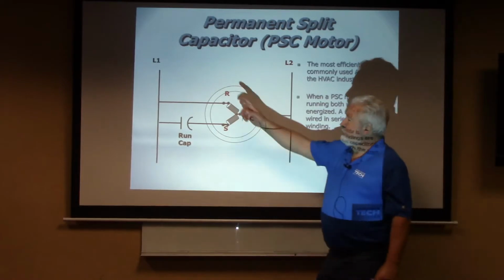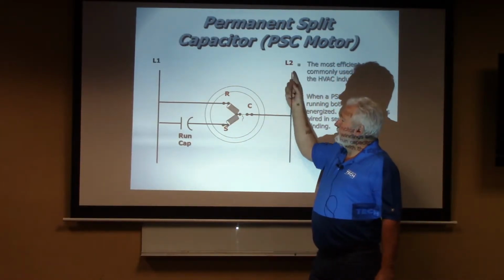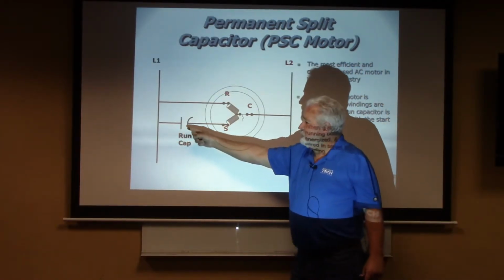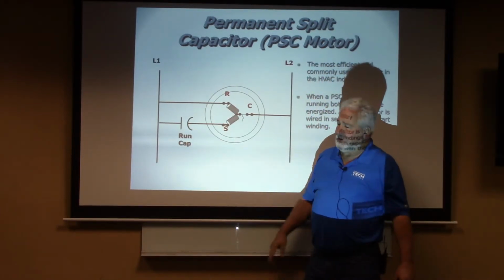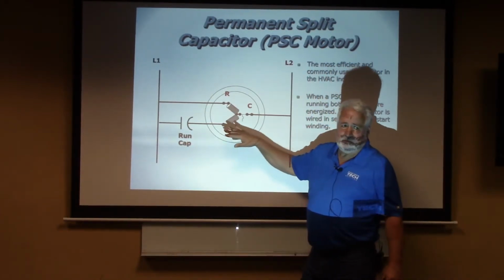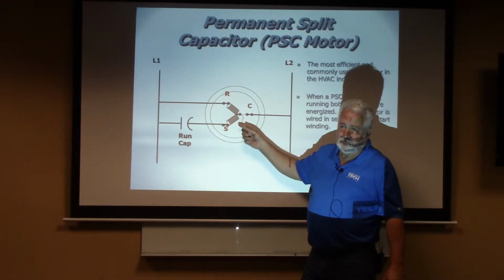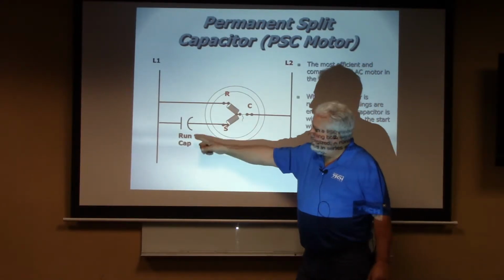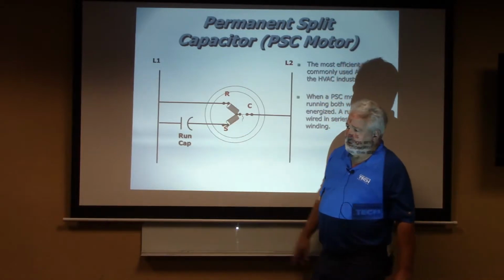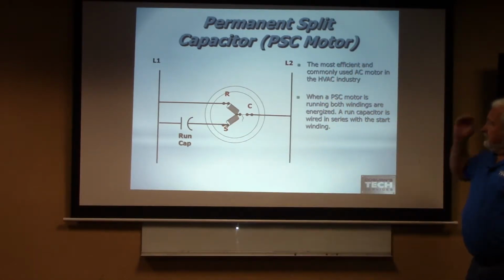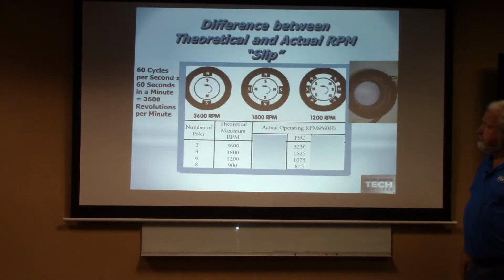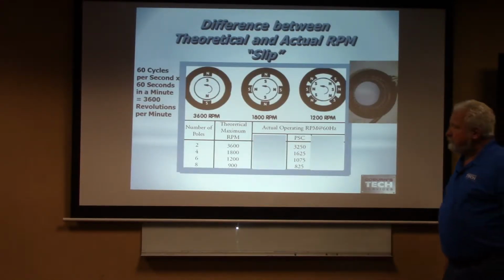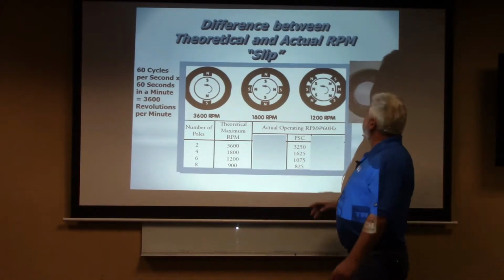You'll see that you have the line 1 coming into the run winding and back to L2, and then line 1 coming into your run capacitor going to the start winding. Run capacitor is in series with the start winding. So when the run capacitor is energized, it will help provide juice to that start winding and help make it operate efficiently. So what happens is we have different poles in the motor.